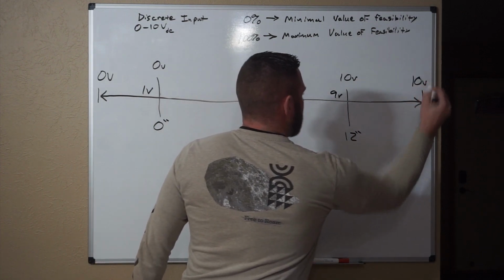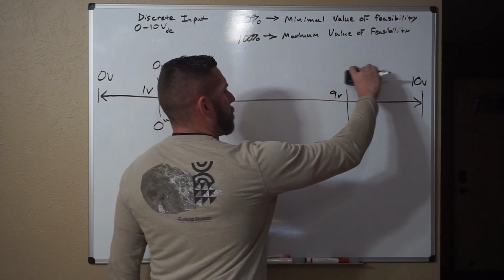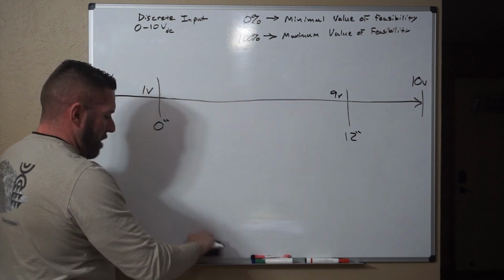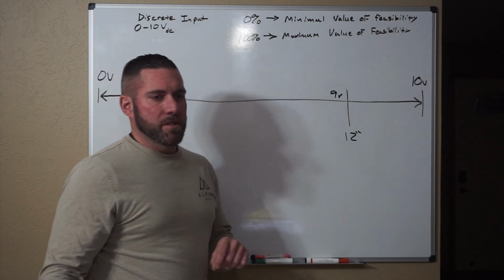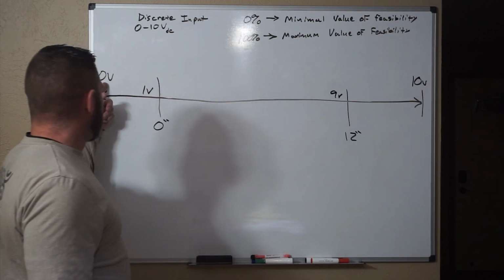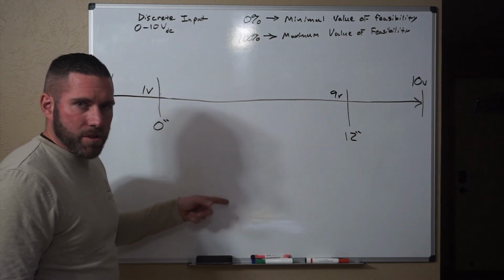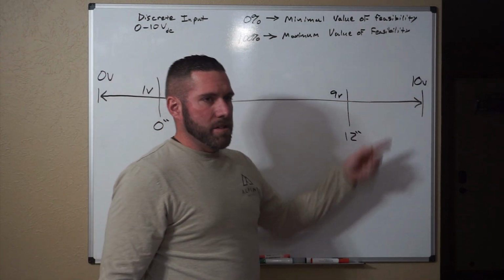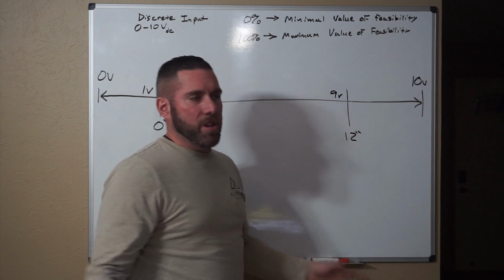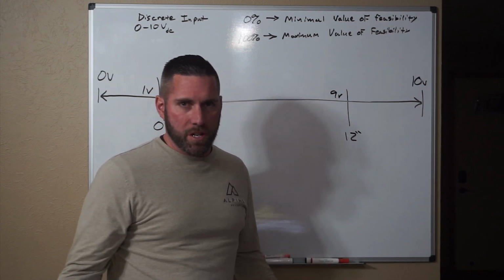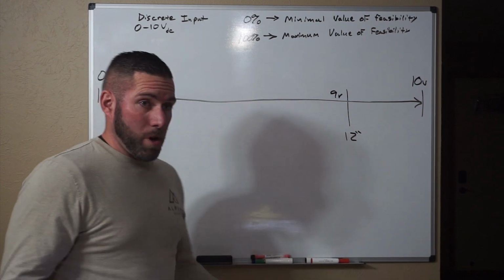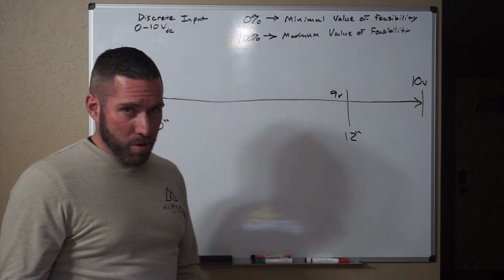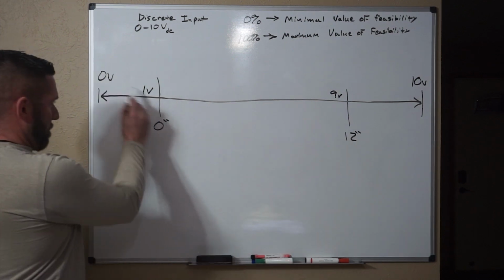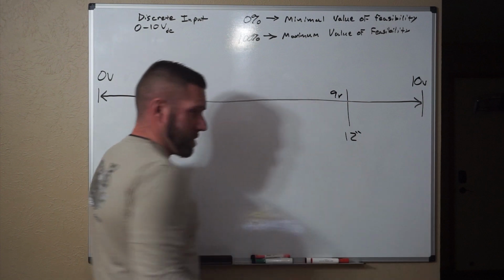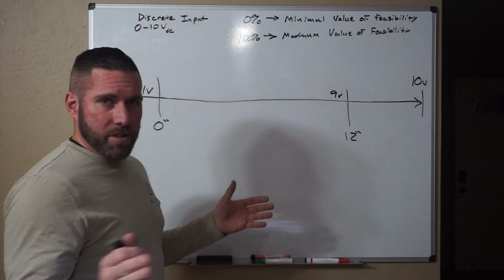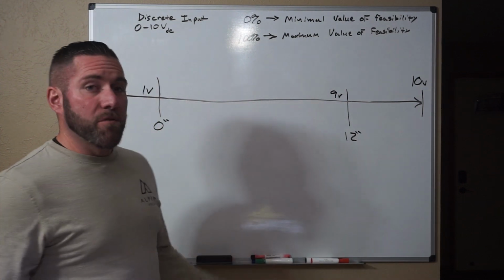And another reason you would make it inside the range instead of making it completely and totally across the full range is you have manufacturing and QC tolerances that don't always mean 0.000000 or 10.000000. Nothing is ever precise. There's no such thing. Otherwise, one manufacturer would monopolize the entire planet. So what we do is we set it inside of the range for tolerances, allowances, potential fluctuations.